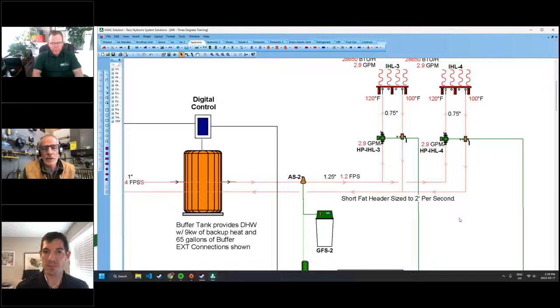Yeah, it's the whole concept of hydraulic separation. So that big tube on the bottom, that 1¼-inch copper pipe, you've got to add the flow of both those pumps when they're operating and make sure that pipe they're connected to, that supply header, can supply them both when they're running full speed, assuming maybe they're modulating pumps or something like that. But you've got to have the capacity there for both those pumps running.